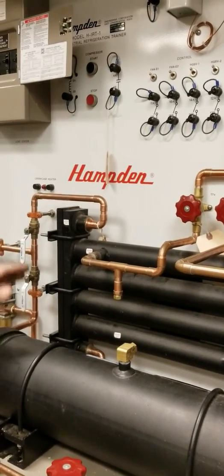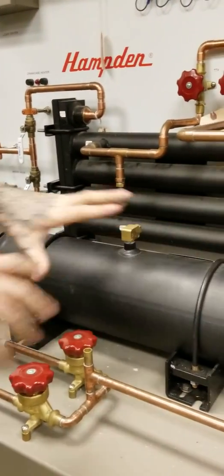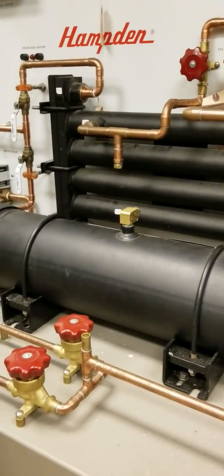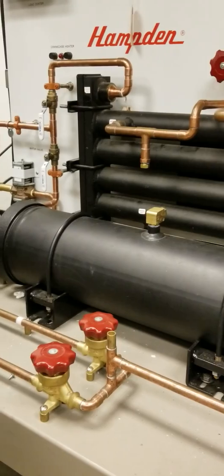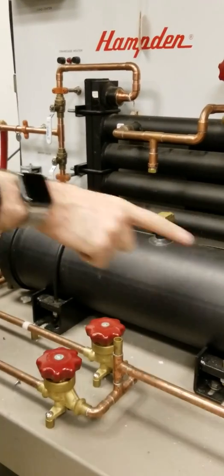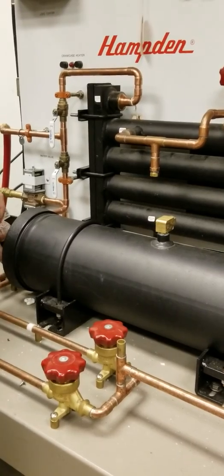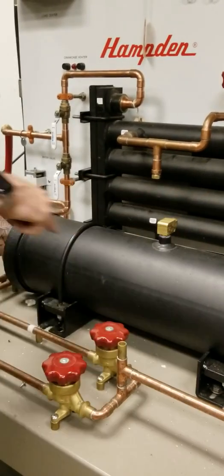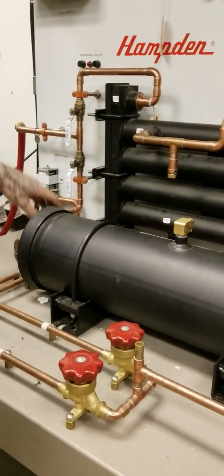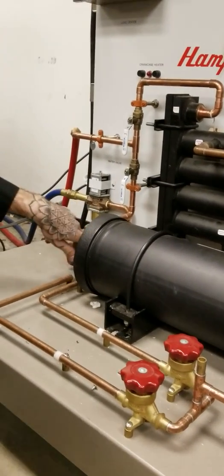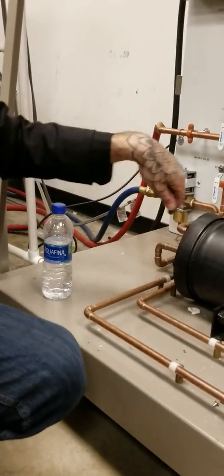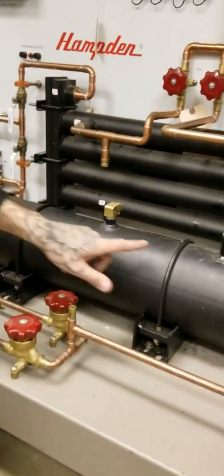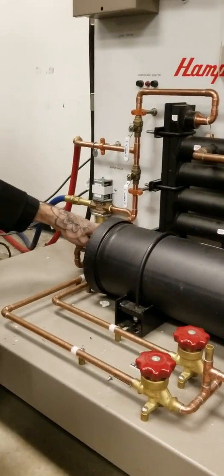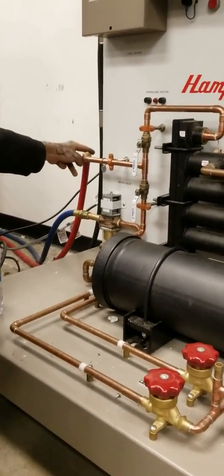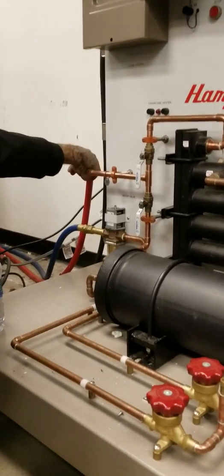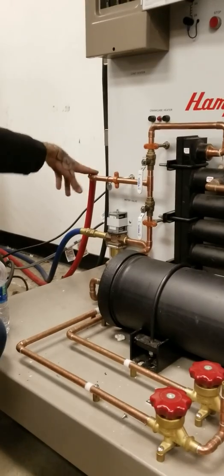With this design, similar process, your hot gas fills the shell of the container, and your cold water will come into the bottom. You could have multiple different styles of this, where it'll have a 2-pass, comes in and comes out. You could have a 4-pass where it comes in, comes out, comes in, comes out, 4 times, you have 4 pipes in there. This looks like a 2-pass. So the water is going to travel through its tube, do a U-turn and then leave, collecting heat. And then it leaves through this red hose where it's going to go to the top of the cooling tower to have evaporative cooling occur and have its heat rejected from the water.